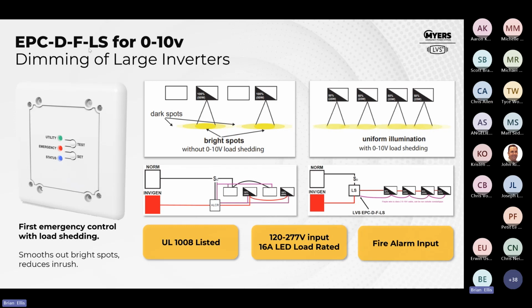So there are some pretty cool applications that we can utilize with this device because of its functionality. One of which is we can provide a load shedding function. So you remember our micro dimmer or our micro inverter? What was great about the micro inverter is it inherently had the 0 to 10 volt controls so that it could dim those. But it wasn't set at a particular level. It was based on a ratio of the wattage of the inverter and the wattage of the emergency load, right? And it's always going to output its wattage, and that's how you do that.